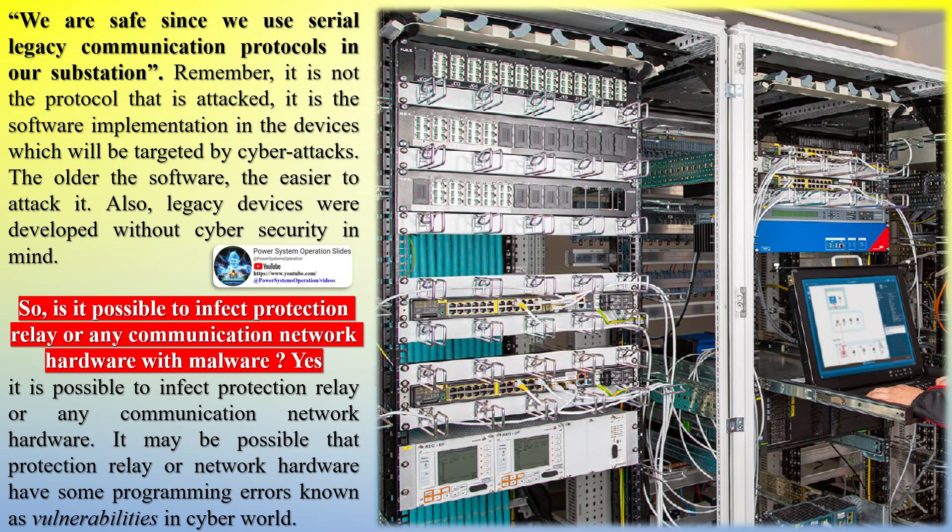Another myth: 'We are safe since we use serial legacy communication protocols in our substation.' Remember, it is not the protocol that is attacked — it is the software implementation in the devices which will be targeted by cyberattacks. The older the software, the easier it is to attack. Also, legacy devices were developed without cybersecurity in mind.